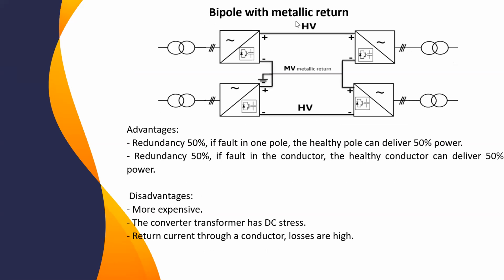And then for bipole, it is almost the same as asymmetrical. We have a metallic return. So what is the difference for bipole? We have two poles here, one pole here and the second pole here. This is actually like a combination of asymmetrical monopoles. For metallic return, each pole can transfer 50% of the power. So in case of any problem with one conductor or one pole, we can still transmit 50% of the power. The disadvantage here is that it is more expensive, because we have more equipment in every substation, almost 2 times in terms of valves and other material. And then the same here, because we are using metallic return.